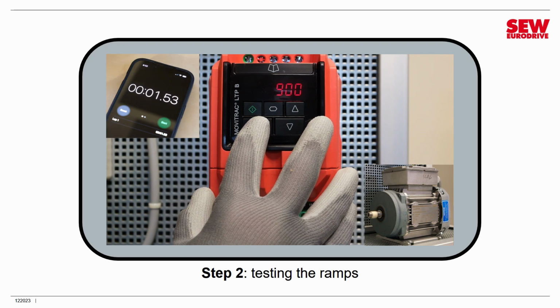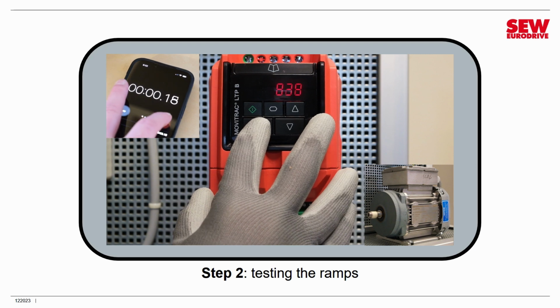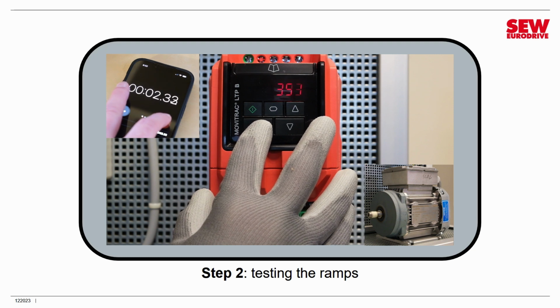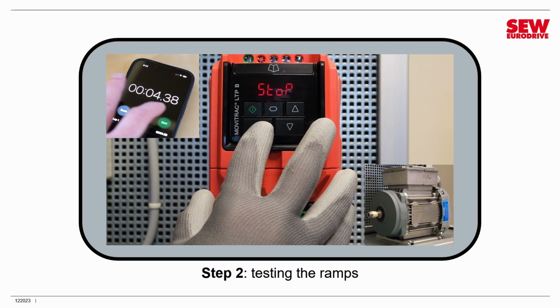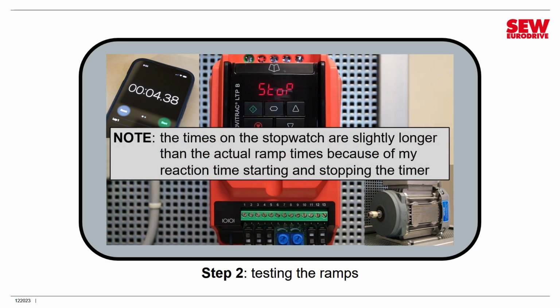We're now going to reset the stopwatch and we're going to bring it to a halt by pressing the stop button, and we'll time the down ramp. Here we go. All right, and you can see that took the 4 seconds we were supposed to program in, so everything worked great. Pretty simple.